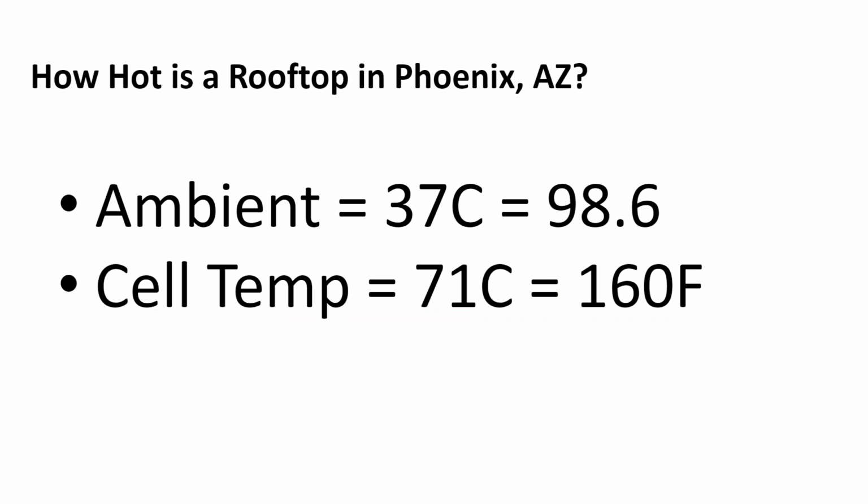So I think that we need to appreciate how hot it gets on a roof. Electrical components have temperature ratings, and the wire terminations, where one wire is spliced onto another, tend to be the hot points of the system. When you're transitioning from the rooftop into the attic, there's going to be terminations.